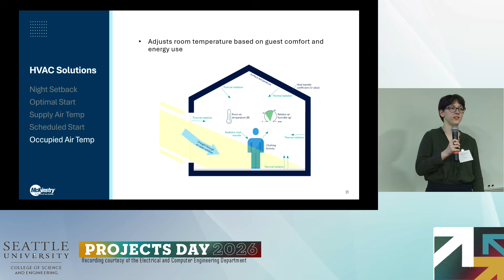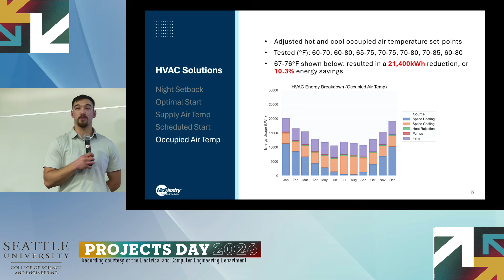Lastly, we have the occupied air temperature adjustments. We wanted to test expanding this band of just what temperature we allowed it to be indoors in these zones, and we wanted to balance that with guest comfort. For occupied air temp, we tested a multitude of values in different bands. We tested 5, 10, 15 degree bands. We even tested a floating band, which would take monthly energy usage data between different set points and choose the lowest out of that to create a dynamic set point. However, we had to make concessions to guest comfort. So we chose a moderate comfort level, which was about 67 at the lowest end to 76 at the highest end. This resulted in a 21,000 kilowatt hour energy reduction, or about 10.3% energy savings.